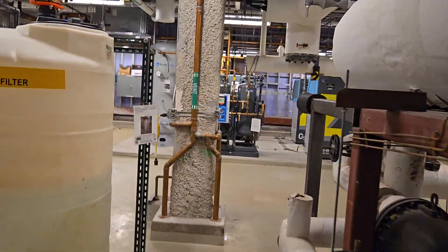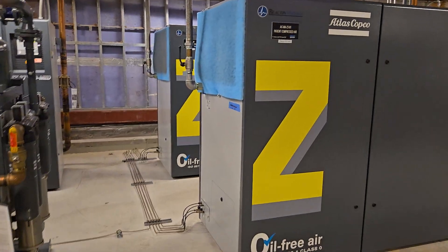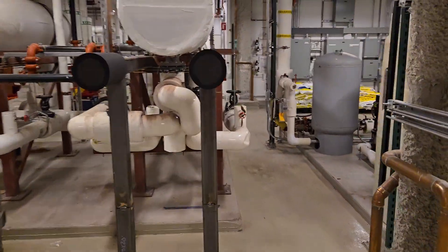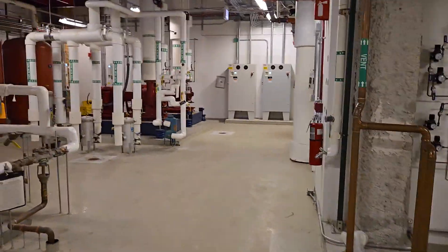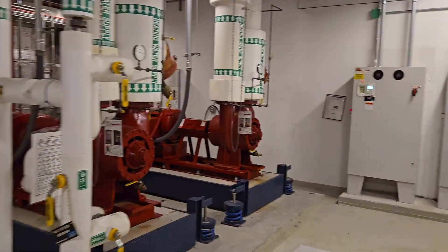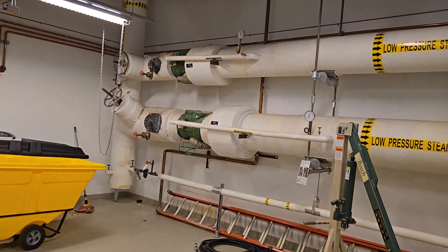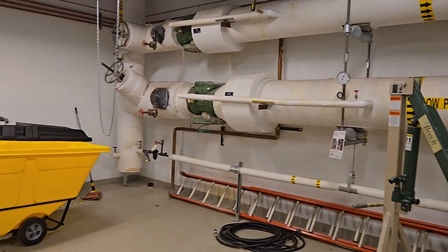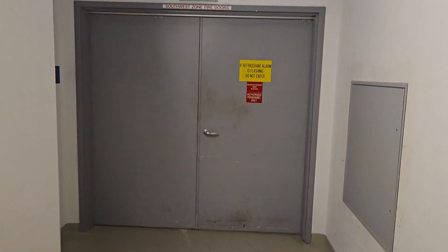These machines are very critical to the hospital. These boxes with the big Z on them are patient compressed air. If these go down, nurses will be bagging children who need oxygen — and that happened one time; it wasn't fun. Secondary piping room also has step-down steam from the boiler room. These big step-down valves take 150 pounds of steam and make it into 10 so it can go throughout the hospital. These are Spence valves — like step-down transformers, but for steam.